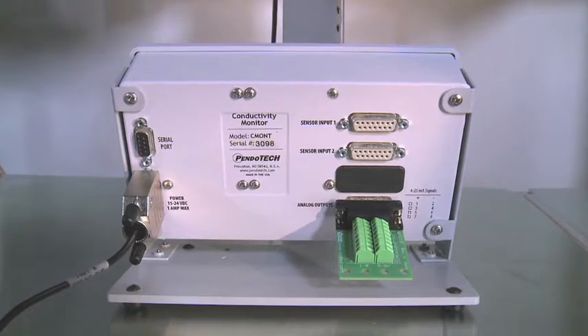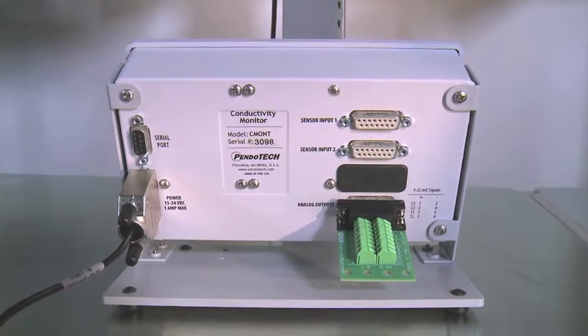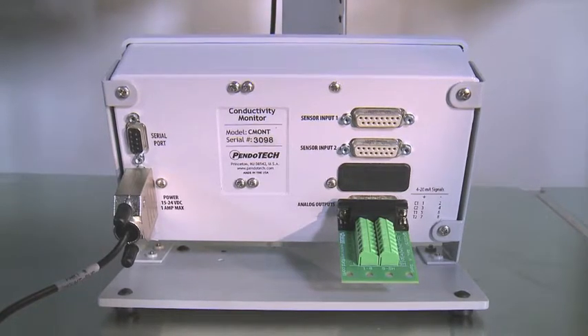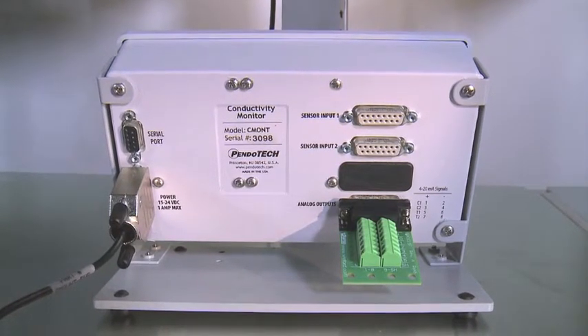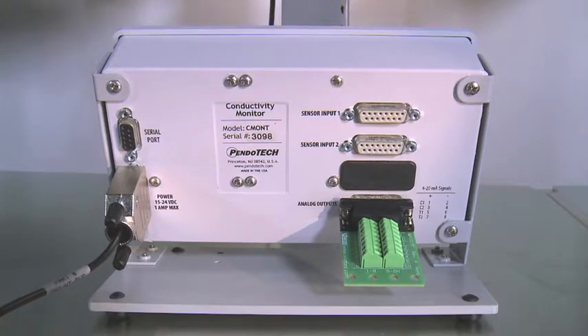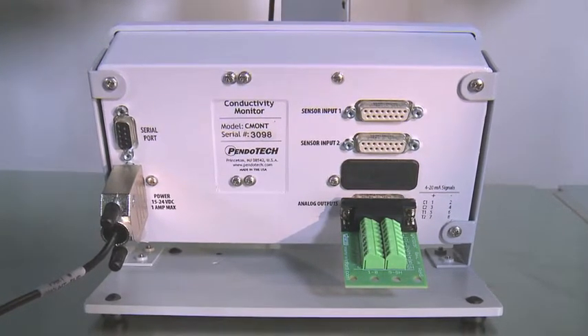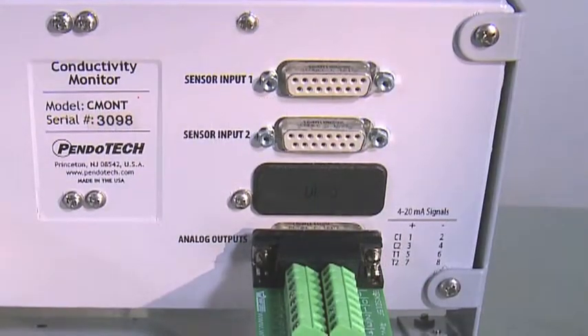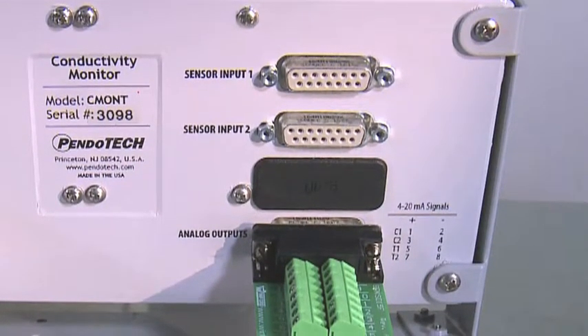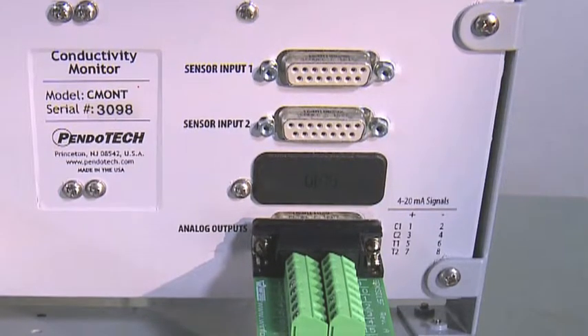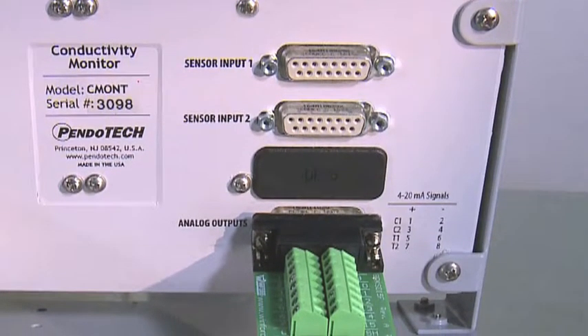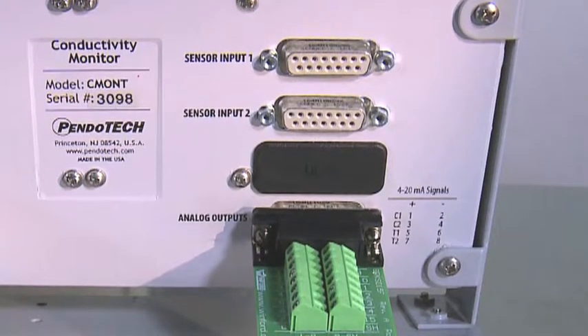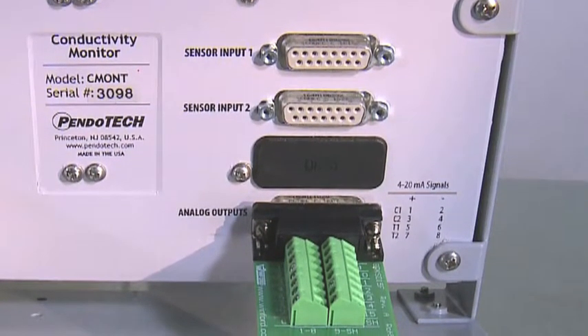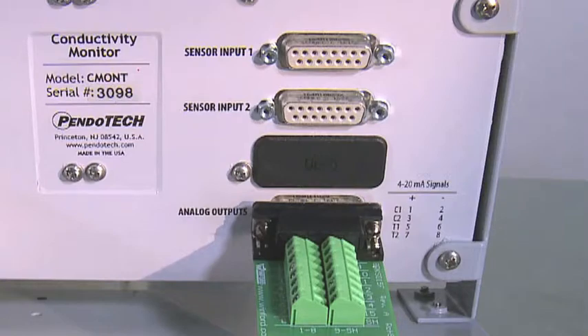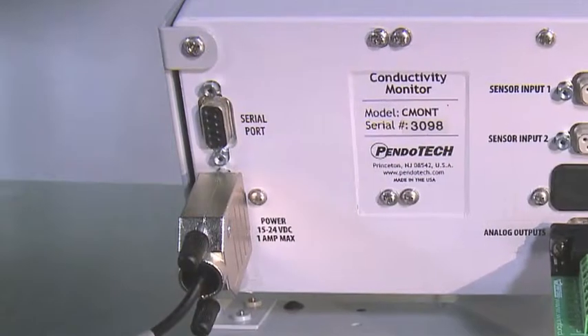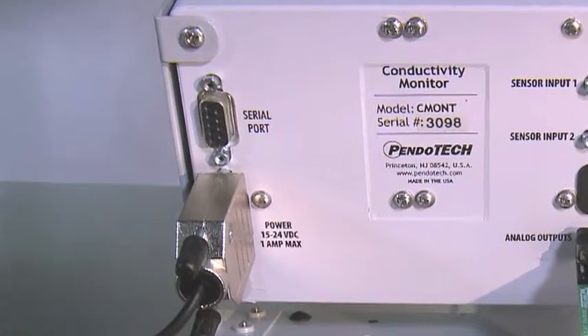The unit is powered by a 24-volt power supply that can be connected to any wall outlet and the display turns on. The reusable monitor cables plug into the back panel. For applications where it is desired to have the conductivity and temperature readings displayed in another location, for instance, a process controller such as a PLC or Delta V, there are 4 to 20 milliamp analog outputs for both conductivity and temperature. These signals are accessed via the screw terminals on an included breakout board. There is a serial port most frequently used for data acquisition to a PC.